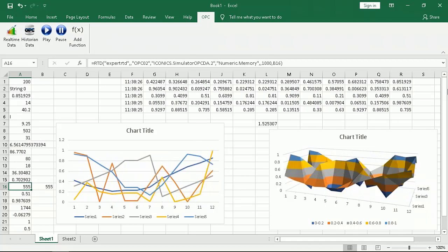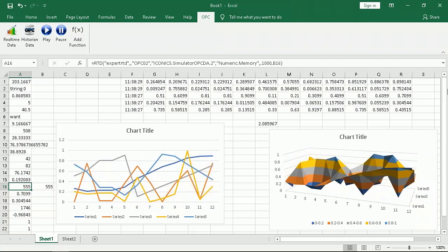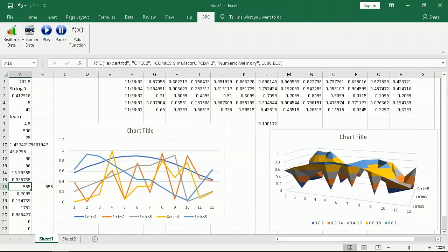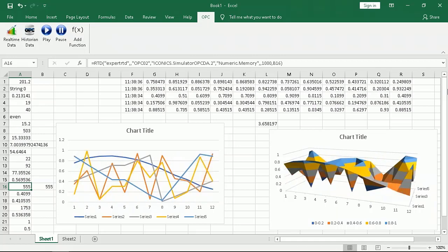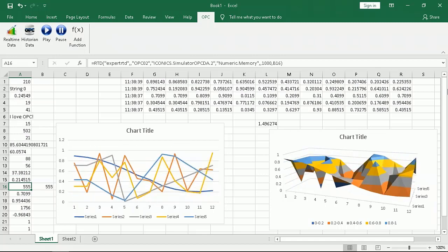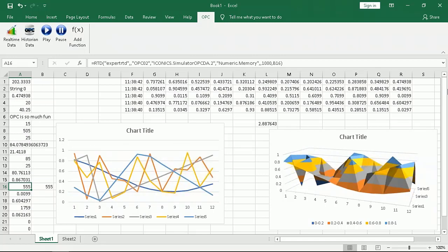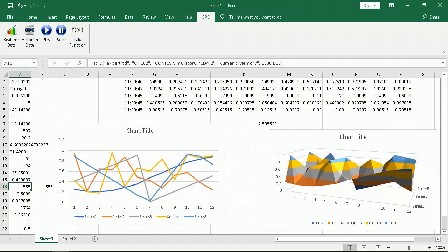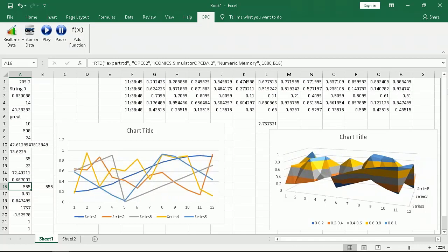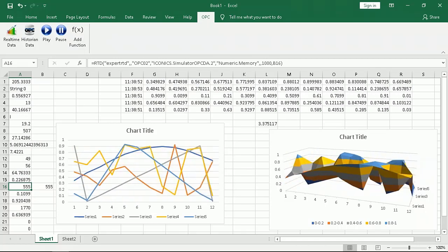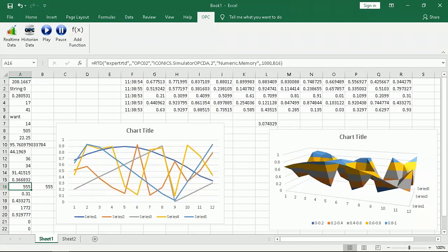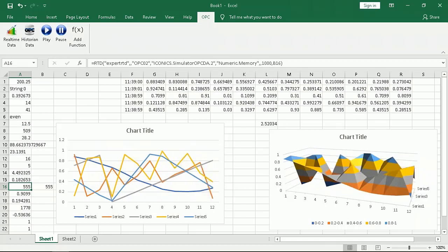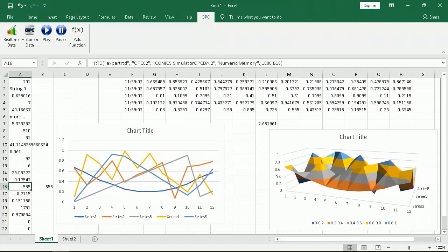Isn't it possible to protect cells and sheet in Excel? Yeah, absolutely. Good point, Giacomo. This is what I was saying, that you can disable stuff in Excel. But remember, if a point is read only in the OPC server, this thing cannot do magic and all of a sudden write to it. Also, if your point is read write, people will be able to write to it. You can stop them from Excel, you can protect the cell and so on, but they'll be able to write from another application. But of course, not from your sheet. So yeah, you're absolutely right. You can stop people.